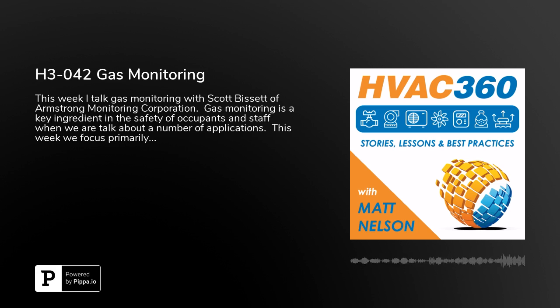So, I guess, would that just be a sound alarm, an audible alarm? We've seen it done a variety of different ways. Our monitors themselves include audible alarms, and are certainly available with strobe type devices as well. We manufacture and provide multiple audio-visual combination devices. We don't see them used terribly frequently in commercial parking applications, but there are certainly some that will have alarm lights come on when a high level is detected.